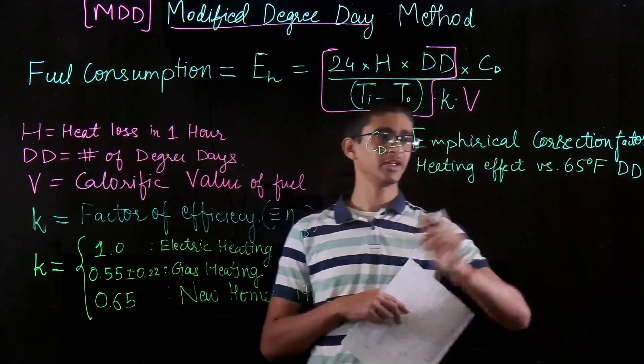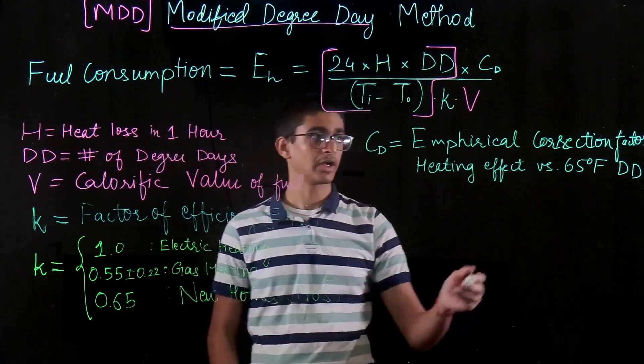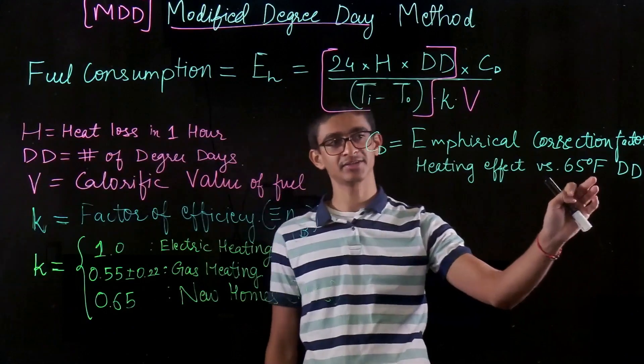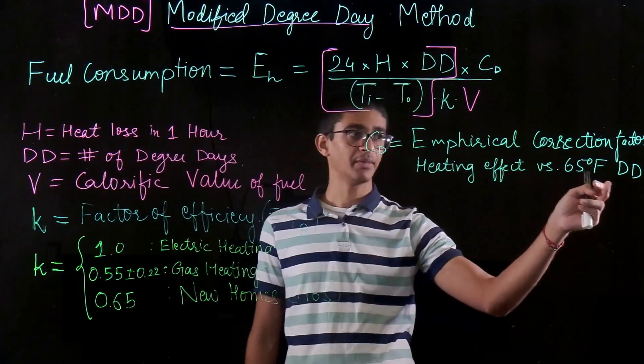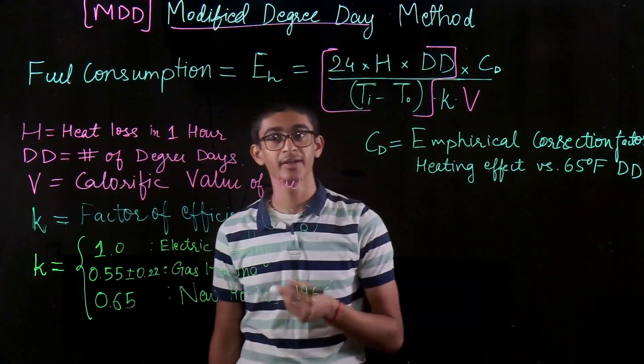So usually the degree days which are recorded in our history are all based on 65 degree Fahrenheit as a balanced temperature. But the balanced temperature can change based on the comfort requirements, the internal heat gains of the building, etc.